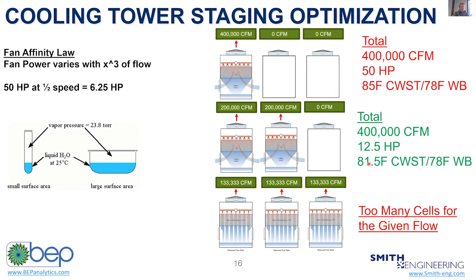So now I'm making 81.5 degree Fahrenheit condenser water with a substantial reduction in fan power. So now I have a choice to make. Do I want to increase the horsepower back up and drive this water even colder? Or do I want to drive this set point back up? And that's the next complicated choice that I have to make. But in general, I just saved a lot of energy because I saved a lot of horsepower at the cooling tower, and I'm going to save a lot of power at the chiller because I have definitively dropped the lift on the chiller, which is going to reduce the power consumption of the chiller.